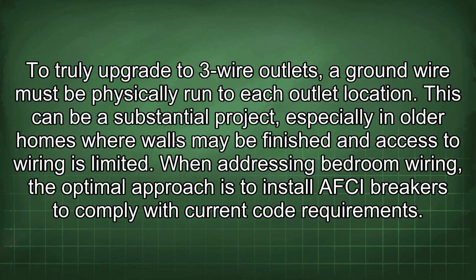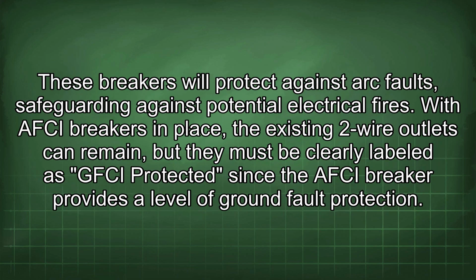limited. When addressing bedroom wiring, the optimal approach is to install AFCI breakers to comply with current code requirements. These breakers will protect against arc faults, safeguarding against potential electrical fires. With AFCI breakers in place, the existing 2-wire outlets can remain, but they must be clearly labeled as GFCI protected, since the AFCI breaker provides a level of ground fault protection.